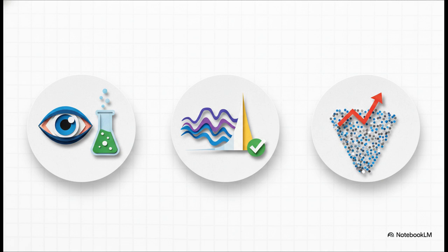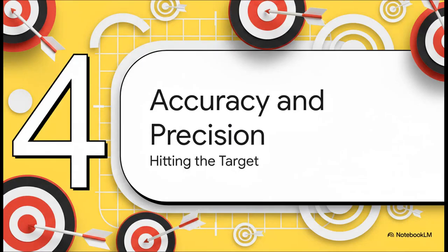Look, what matters here isn't memorizing all these dense formulas. It's understanding that whichever method you choose, your quantitation limit should be equal to or below your reporting threshold. And often, it needs to be validated directly by accuracy and precision testing right at that lower limit. Which brings us to Section 4, Establishing Accuracy and Precision, Hitting the Target.